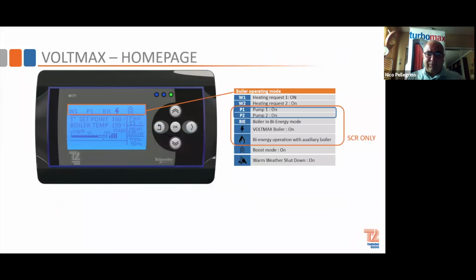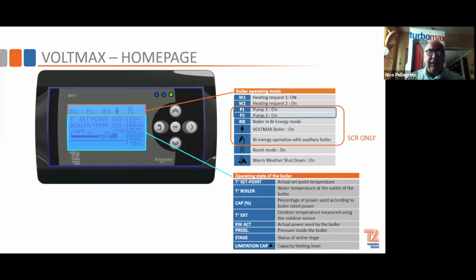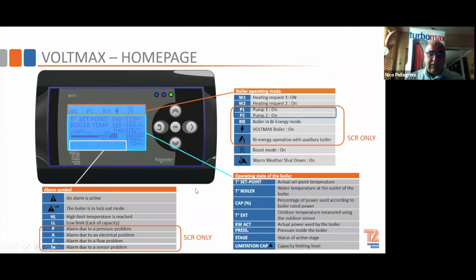As I said, the display is just like the Ultra Smart controller. It tells you everything that's happening. So you know whether your pump is on, you know at what capacity you are, you know your stages, your temperatures, your kilowatts, and your pressure. Also, on the SCR models, you get all your different alarms and pressure problems, electrical flow problems. All the sensors are displayed at the bottom. And then obviously your warning lights: red is you've got a problem, yellow, there's something going on, and green is all good.